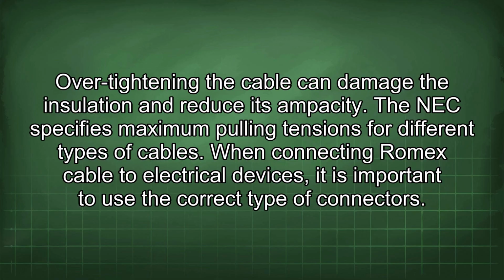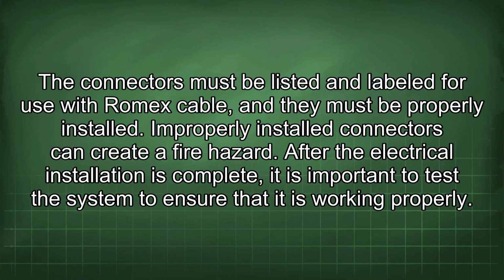When connecting Romex cable to electrical devices, it is important to use the correct type of connectors. The connectors must be listed and labeled for use with Romex cable, and they must be properly installed. Improperly installed connectors can create a fire hazard.